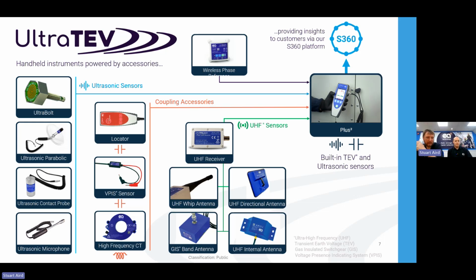Linked to that, we've added a GIS band antenna. So this allows us to look at more the tubular GIS on the spaces for supporting spaces. Again, typically 132 kV and above, and allows us to do spot measurements on the large GIS installs. From an OEM point of view, or from a retrofit internal install, we've brought out internal antennas, and you'll find them installed right across the market now, typically in cable boxes, and they'll provide coverage of that whole compartment, again linking out to the handheld device.